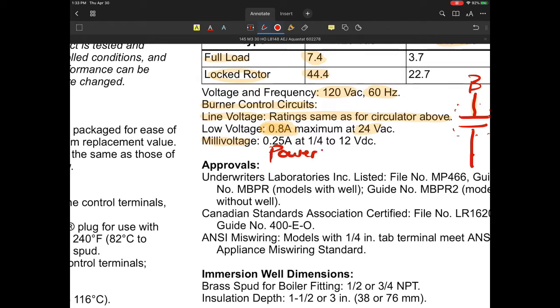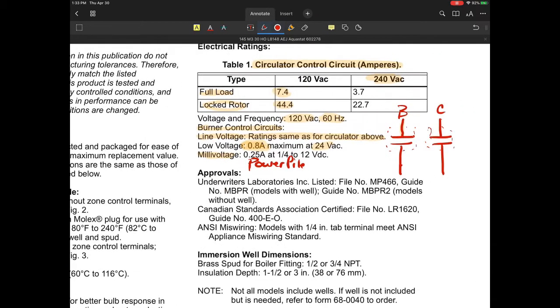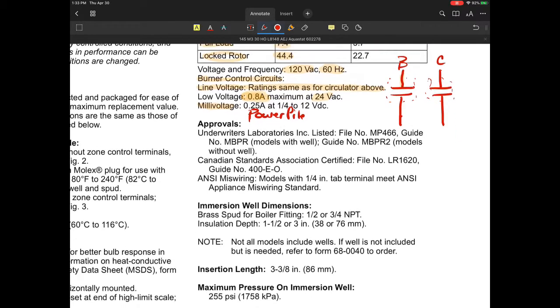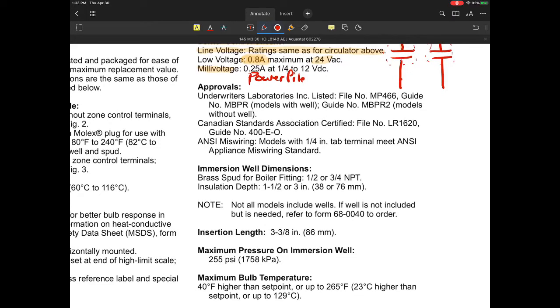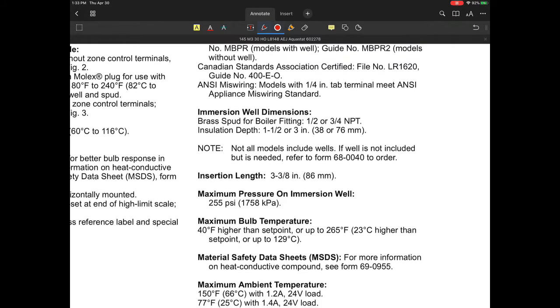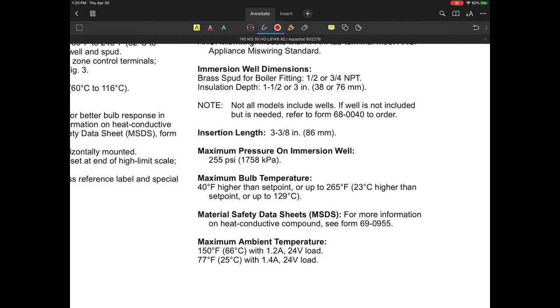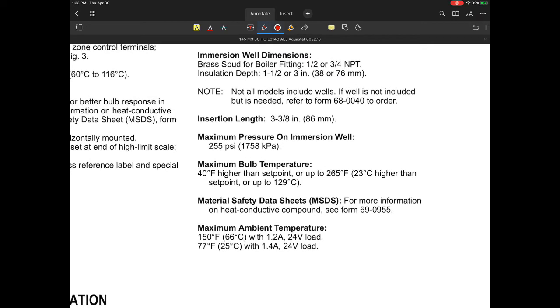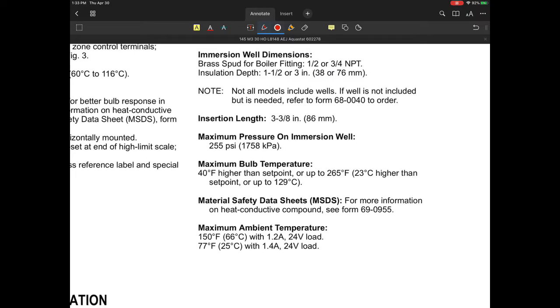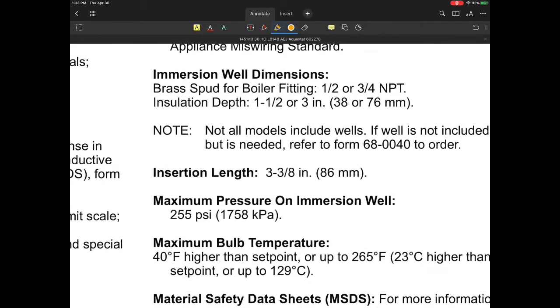The millivoltage, this would be typically your power pile stuff. So most of the time when we start looking at this, your power pile is your 750 millivolt type of boiler control system. So they might actually have some of those types of things out there, and it works pretty nice. It's not too terribly bad. All right, the approvals, that is fine. I'm not worried about that. If that's something you have to meet, then you have to verify that yourself.